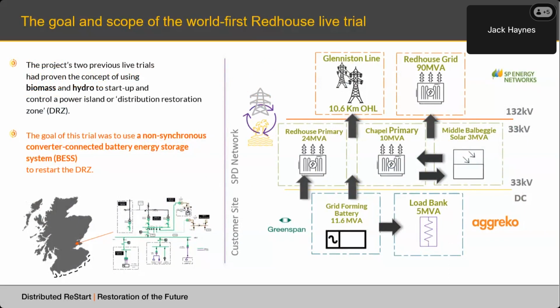You can see a snapshot of the test network that we had set up for the series of tests over the 2-week period in the bottom left-hand corner there. But I've boiled it down to its main parts. The anchor generator, as I mentioned, was an 11.6 MVA battery energy storage system that had been retrofitted with grid forming technology. It's unusual for battery storage systems to have grid forming technology. That was designed as part of the project.